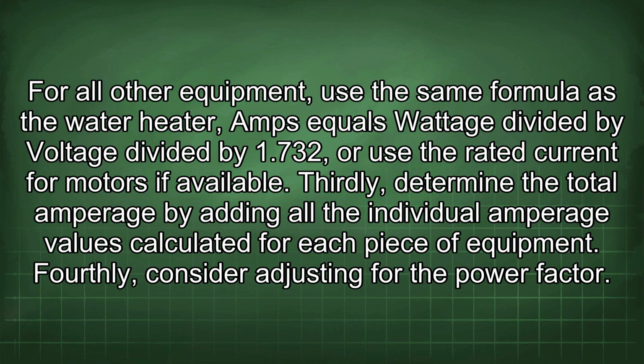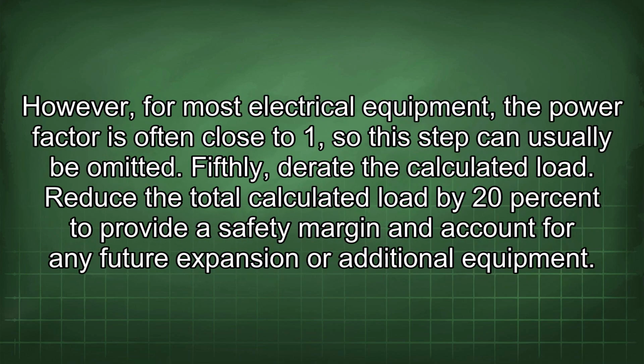Thirdly, determine the total amperage by adding all the individual amperage values calculated for each piece of equipment. Fourthly, consider adjusting for the power factor. However, for most electrical equipment, the power factor is often close to 1, so this step can usually be omitted.